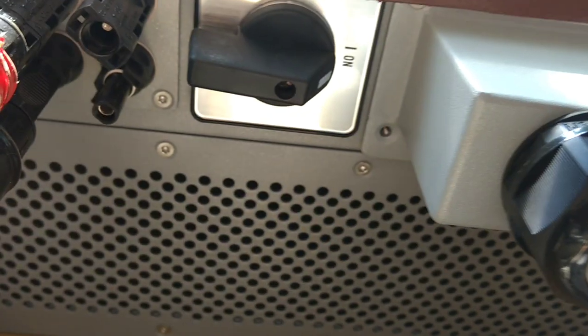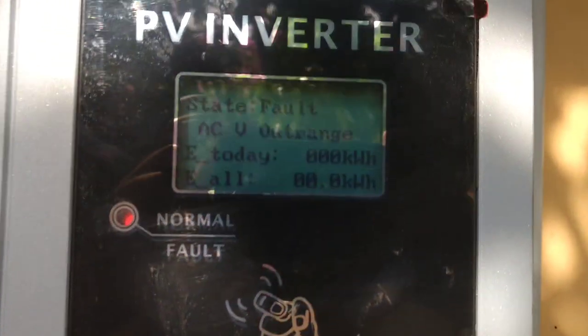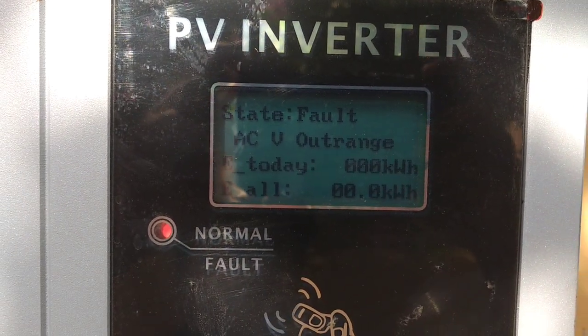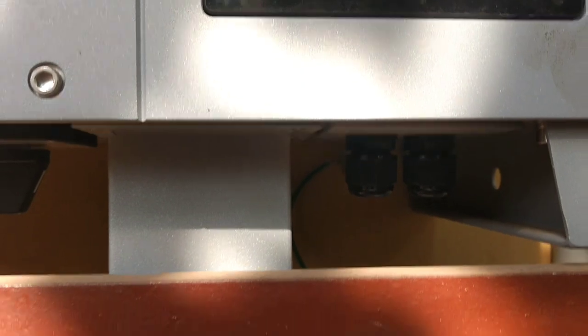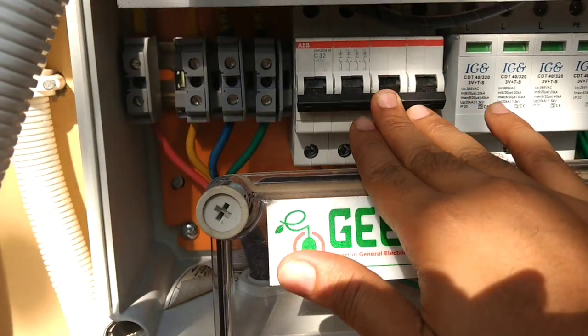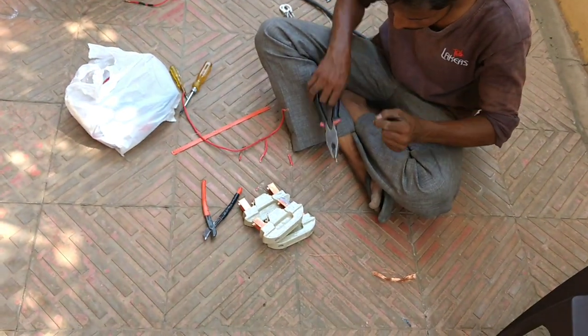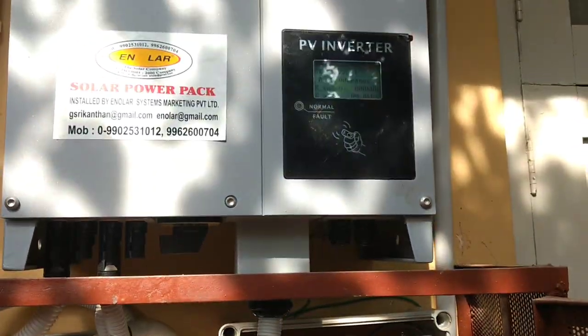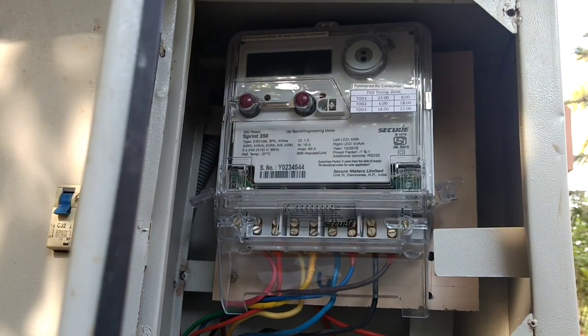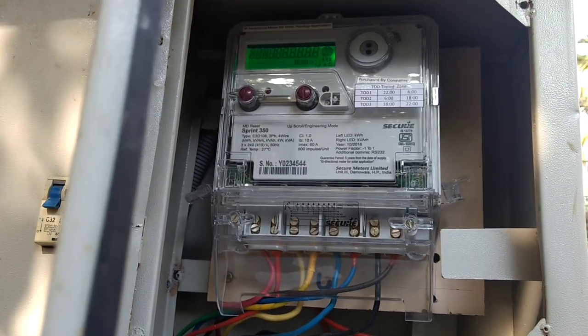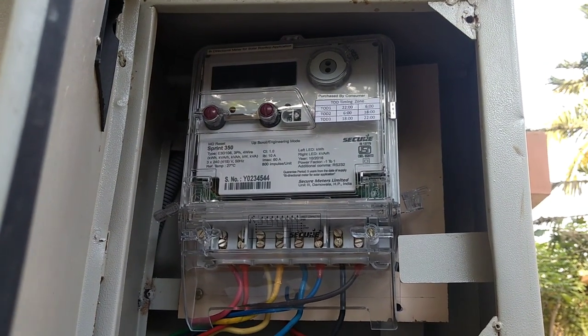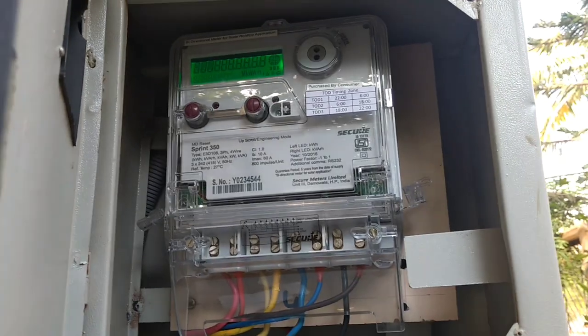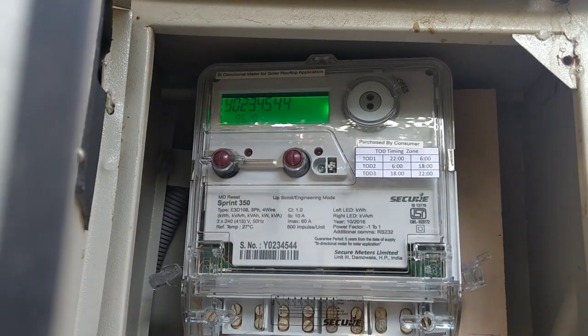Now we are going to turn on the inverter. So I have put on the regulator to the on mode. Now the display is showing a fault that the AC is out of range. That is because just now the inverter is not connected with the grid, and also I've kept the MCB off for better protection. Meanwhile, this person is making the cutout fuse to connect with the grid. Now that person will connect the bi-directional meter to the grid. As you can see, the meter has just started giving the reading. Now we are going to start the inverter.